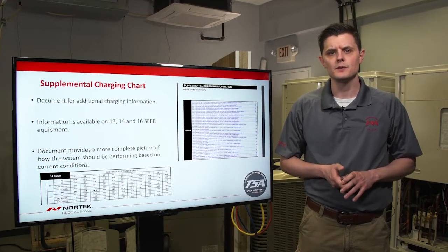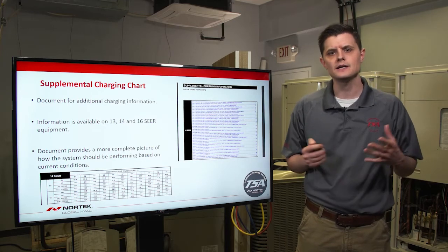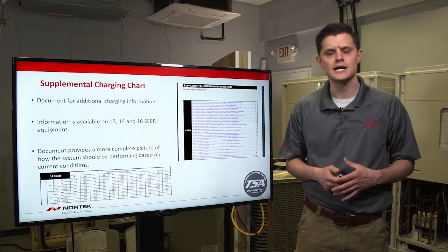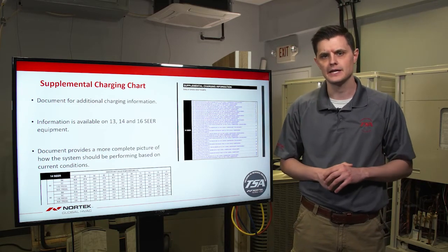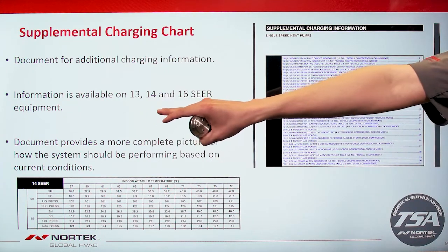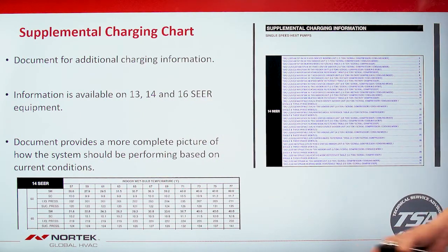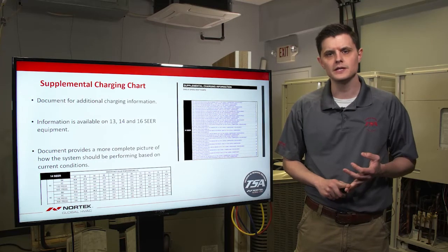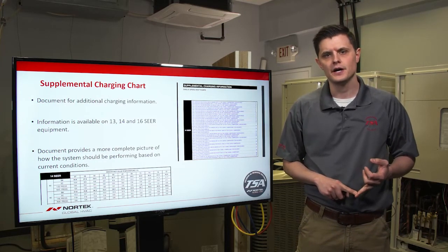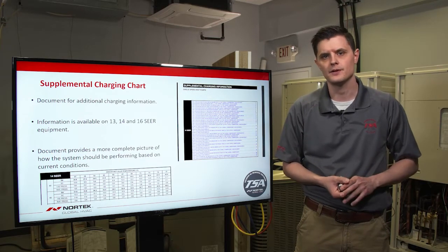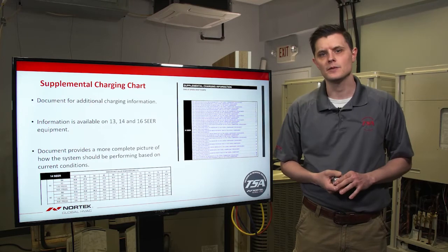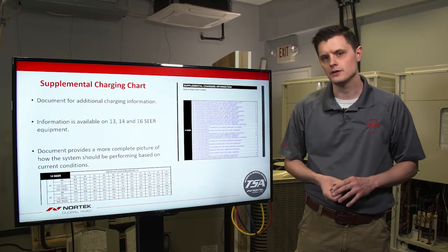The next document is our supplemental charging chart, a newer document developed to help guys charging in the field. It provides more charging information than what's found on the charging sticker on the back side of the condenser panel. This document covers our 13, 14, and 16 SEER equipment and provides a more complete picture of how the system should be performing based on its current conditions. It includes superheat, subcooling numbers, head pressure, and suction pressure numbers—because some guys want to know not just their superheat number, but what their suction and head pressure should be given their current conditions.